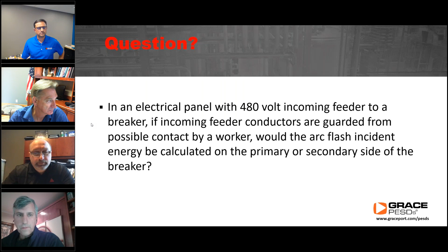The first thing that comes to mind is the industry standards: UL 508A for industrial control panels, and NFPA 79, which provides guidance on building industrial control machinery. When it comes to control panels, it's a totally different animal because it poses multiple voltages. From a product standpoint, we have programming ports or grace ports where you provide engineering controls through the door, so you don't need to open the panel.